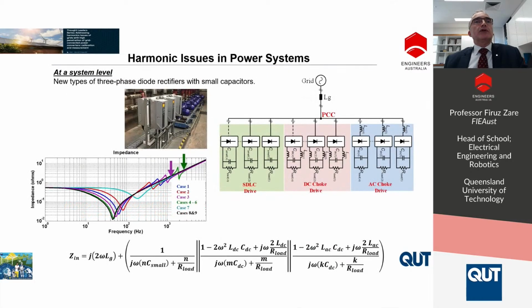But the other important factor to discuss is that even with the diode rectifier that you can see here, there are different types of passive filters for each product that we might have for these types of converters. For example, one of the circuits here doesn't have any inductors in the filtering system. The other one has a DC inductor filter, and the other one has an AC inductor. Each type of filter has pros and cons, but in a production line, when we have different products from different manufacturers, because of their design and filters, we might have different resonances in that private network affecting the quality of the system. Therefore, device analysis is one aspect of harmonic control, and the system is the most challenging, to make sure that all aspects of the design and system parameters are considered.